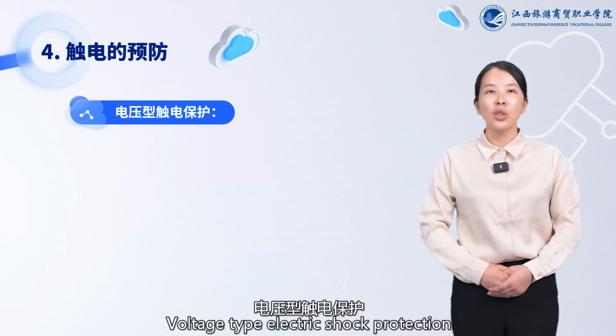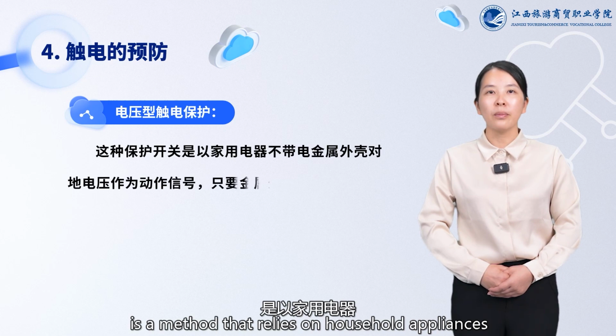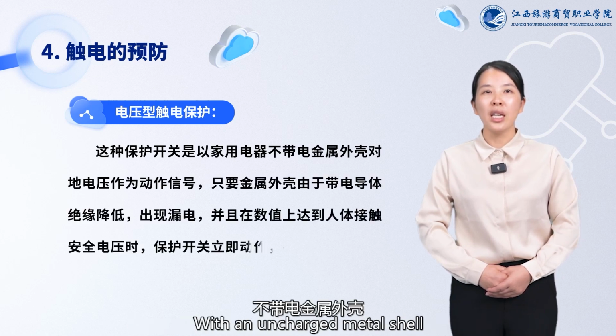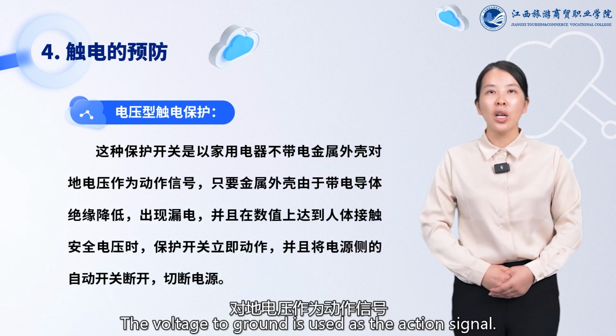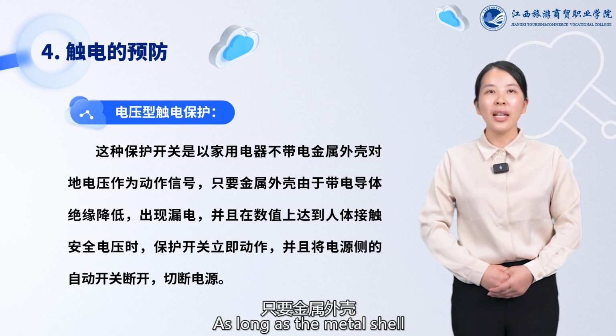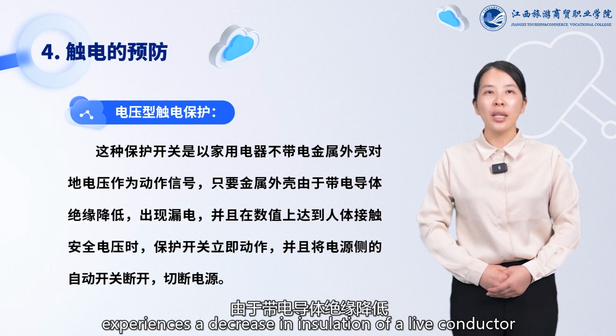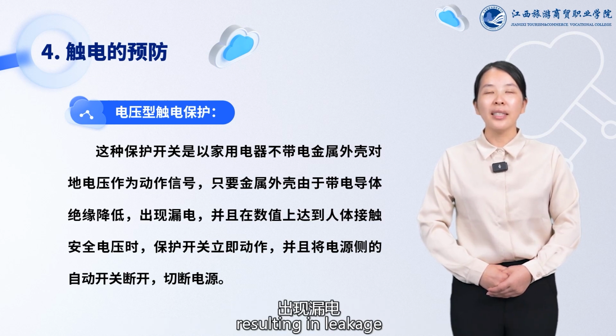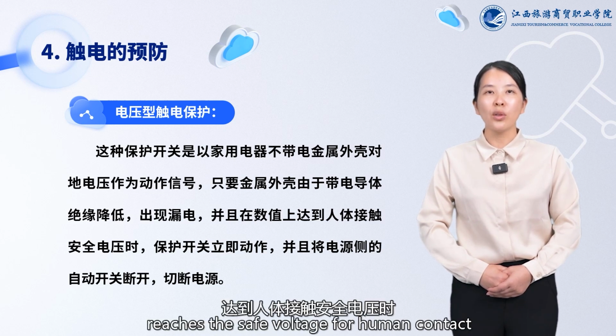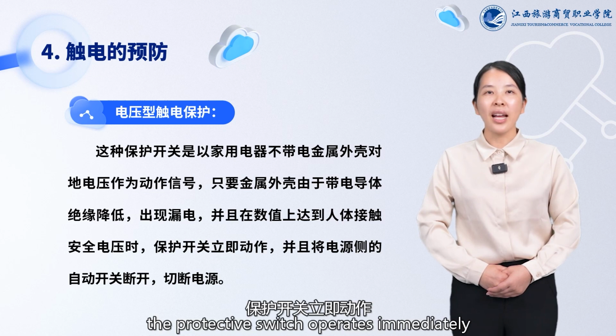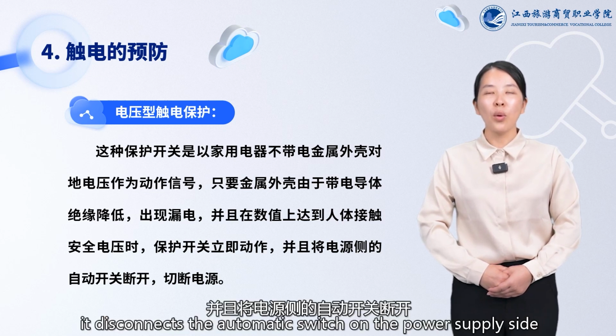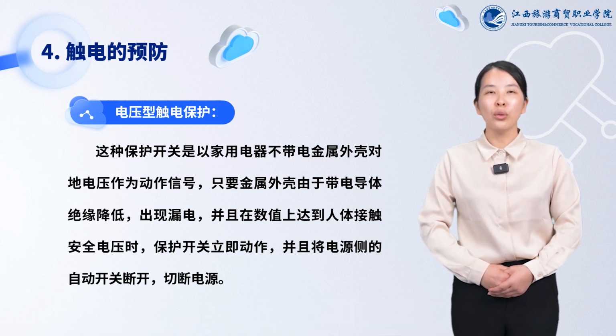Voltage-type electric shock protection is a method that relies on household appliances with an uncharged metal shell. The voltage to ground is used as the action signal as long as the metal shell experiences a decrease in insulation of a live conductor, resulting in leakage, and the numerical value reaches the safe voltage for human contact. The protective switch operates immediately. It disconnects the automatic switch on the power supply side, cutting off the power supply.